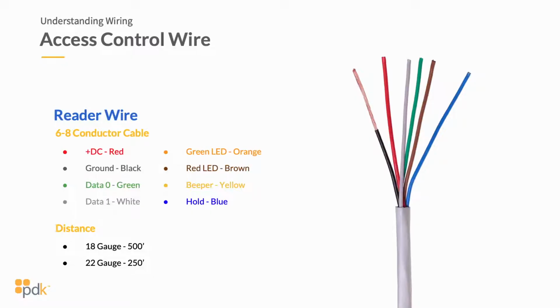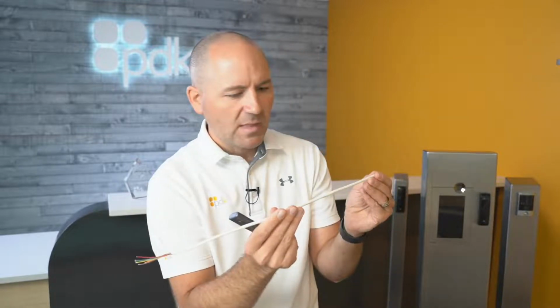If you're running an 18 gauge wire, you can typically run 500 feet. If you're running a 22 gauge wire, you can get about 250 feet. So make sure you're looking at the type of wire you're running. This is a 22 gauge wire here, so you're going to get about 250 feet, and that's very typical for reader wire. It's not very typical that it's 18 gauge. If you need additional distance, move to an 18 gauge wire, but most wire provided for readers is 22 gauge and will give you roughly 250 feet.